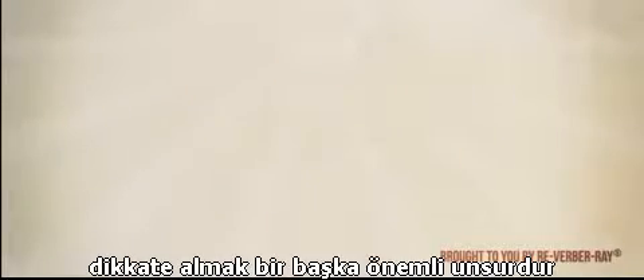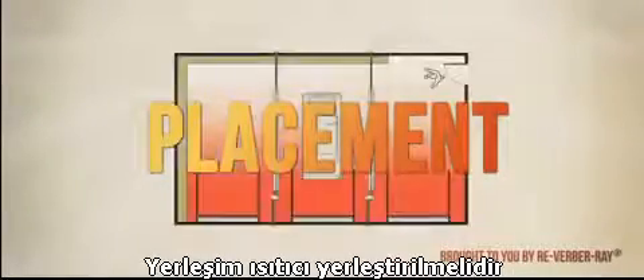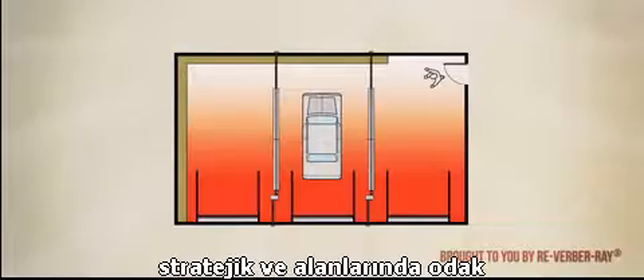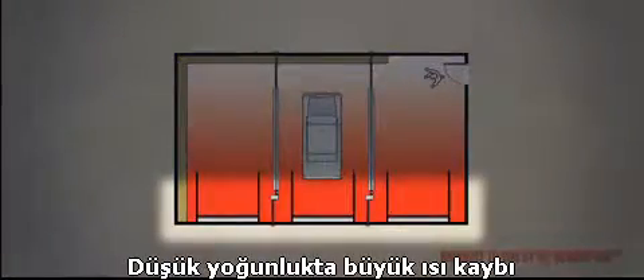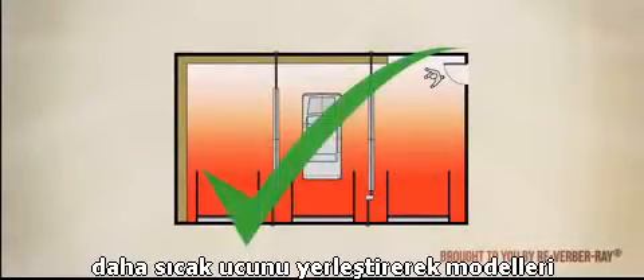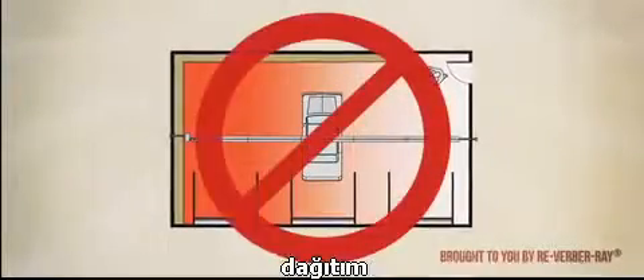Another important element to consider is placement. The heater should be placed strategically and focus in the areas of greatest heat loss. With low-intensity models, placing the hotter end of the heater in cooler areas of the building also helps achieve better heat distribution.